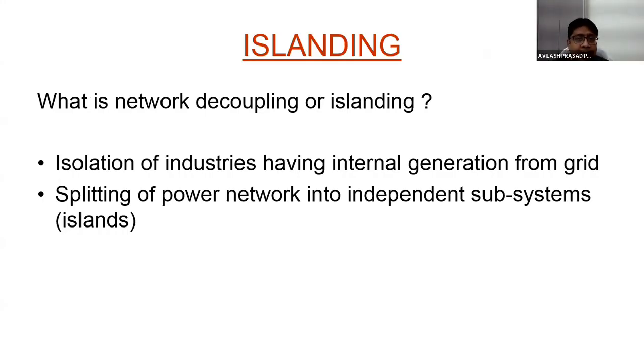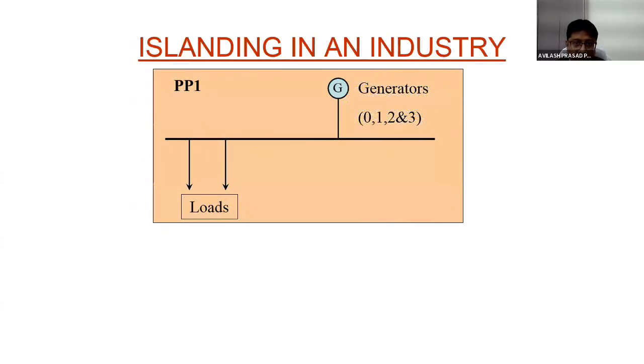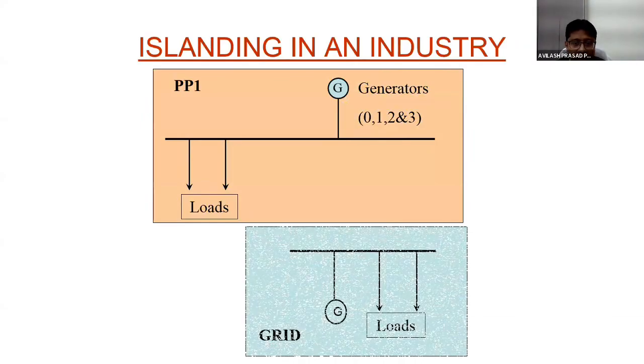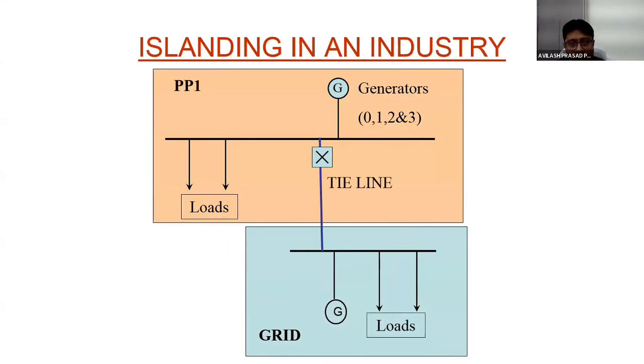Now coming towards islanding, that is acting as a microgrid. When our captive plant acts as a microgrid, what is network decoupling or islanding? Isolation of industries having internal generation from the grid and splitting of the power network into independent subsystems, that is islands. Islanding in industries: as we have PP1, we have 3 generators, 0, 1, 2, 3, and loads are connected to it. And we have the grid, to which various loads are connected. And our captive power plant is connected with the grid with the tie line.